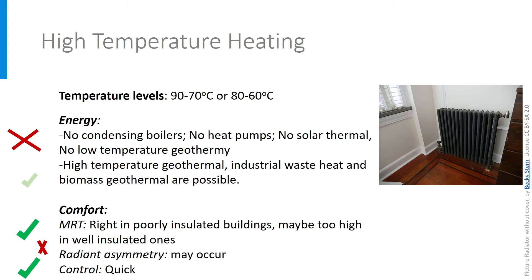There are, however, two interesting things about high temperature heating. The first one is comfort. In general, people love this high temperature source. And most importantly, in old, not well insulated buildings, it helps compensating for much too cold walls and windows during cold days. In short, it increases the mean radiant temperature MRT, especially if placed under cold windows. However, it may also increase radiant asymmetry, and in very well insulated buildings, it could cause a too high MRT. A second advantage is the quick control possibilities — if you come home and switch the heating on, it will deliver immediately a lot of heat and that feels good.